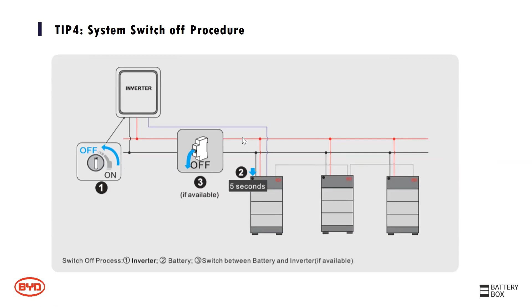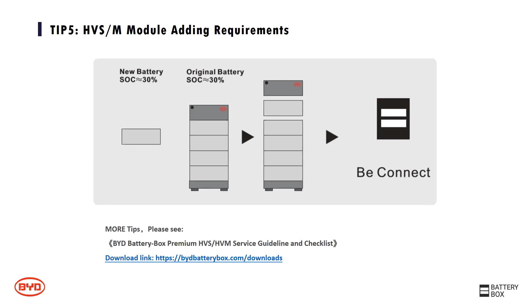Okay, so the next one is the HVM module adding requirement. Just for reference, if you want to extend the battery, it's quite easy and straightforward. When we ship the battery from the factory, each module has roughly 30% SOC. When adding more modules to the existing system, just make sure the existing battery module has a similar 30% SOC, physically install the new modules, and use Be Connect to reconfigure the whole system. That's it - really straightforward.